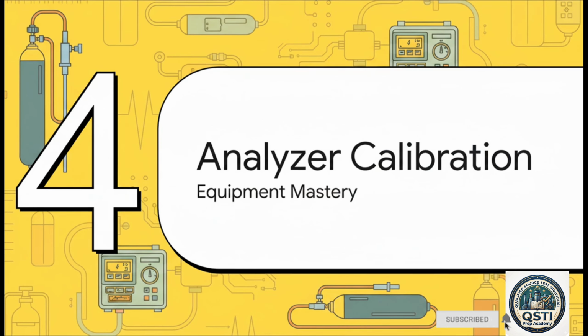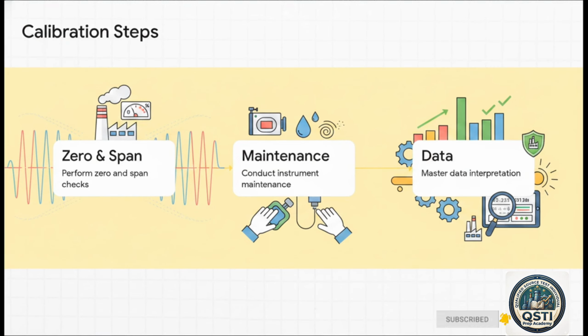Section 4. Equipment and Analyzer Calibration. Let's be real. A gas analyzer is only as good as its calibration, period. The training emphasizes a highly structured, unyielding approach to ensuring equipment accuracy. Step 1. You absolutely must perform strict zero and span checks. This means feeding the analyzer a gas with zero concentration and then a gas with a known high concentration. This establishes your baseline and your exact measurement range, proving the machine is actually responding correctly.